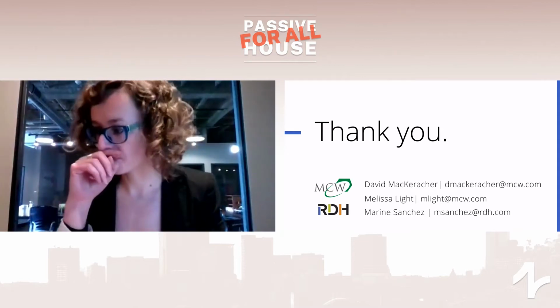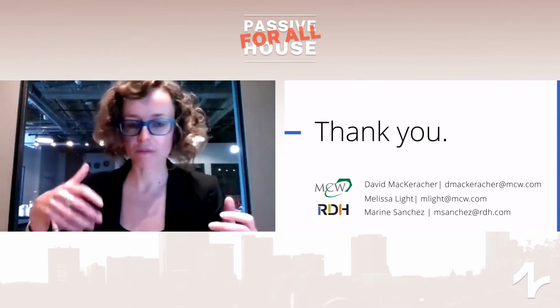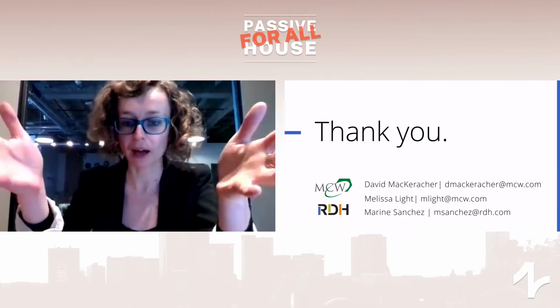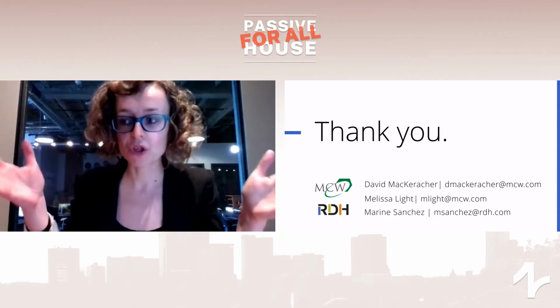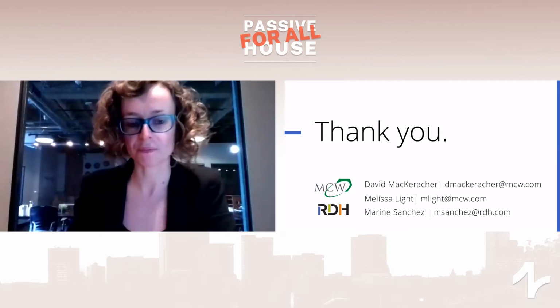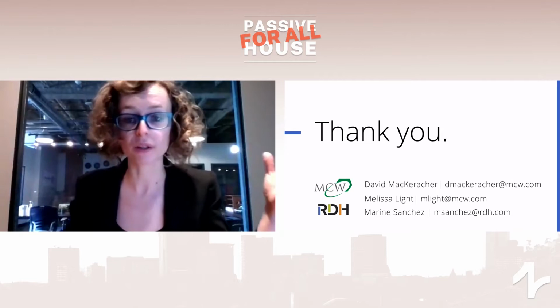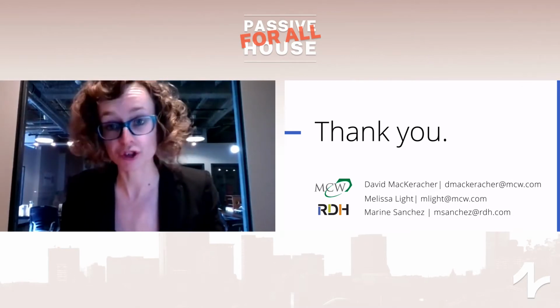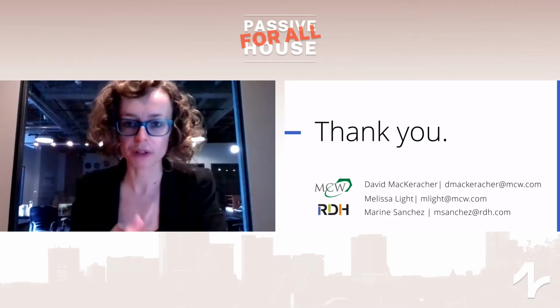So the high efficiency capture hood works almost like the one we presented today. The proprietary system from Halton works with some kind of air curtain that is almost directing the plume at the back of the cooking station, which makes sure that with reduced exhaust flow rate, we are actually capturing most of that plume compared to more standard systems, which would either have a much lower efficiency or would require a much higher exhaust flow rate, which would have a penalty on the energy side to get the same efficiency, to deliver the same service. So this is what we were talking about in the presentation.